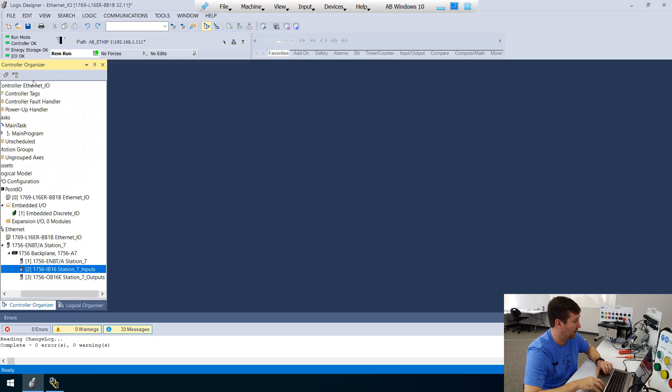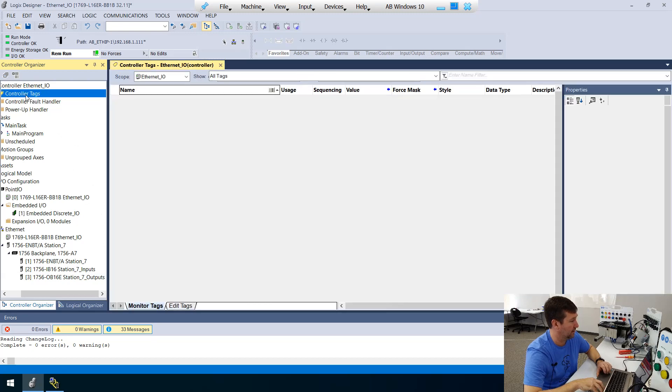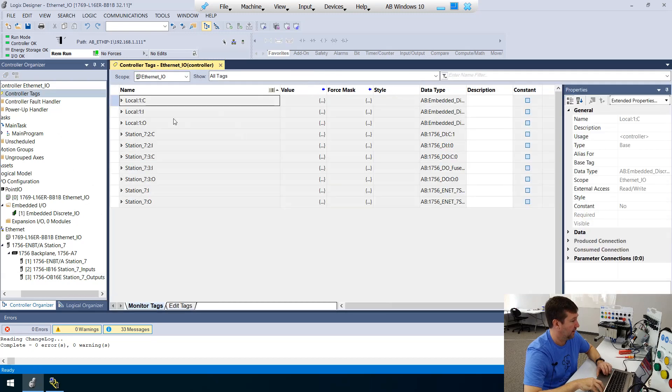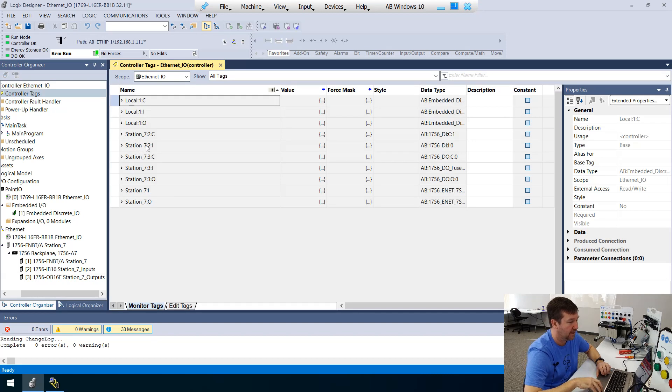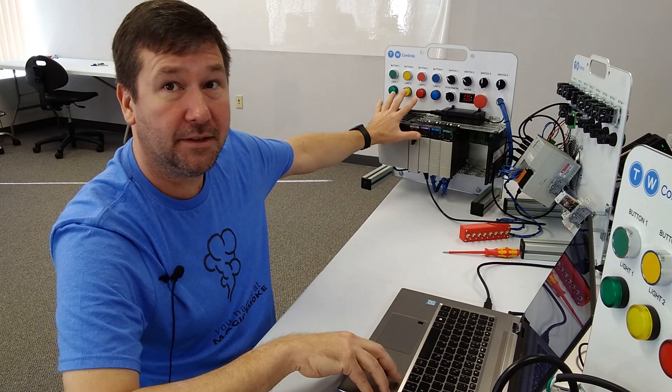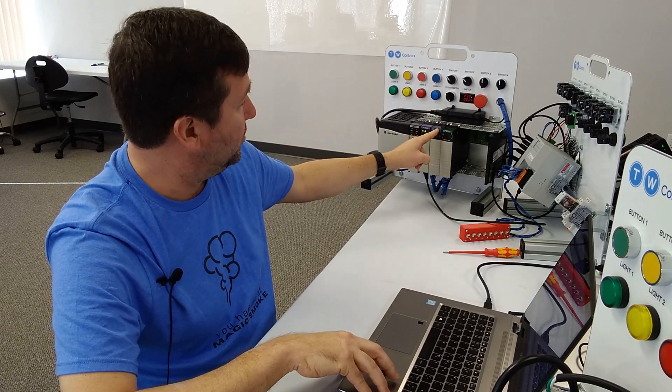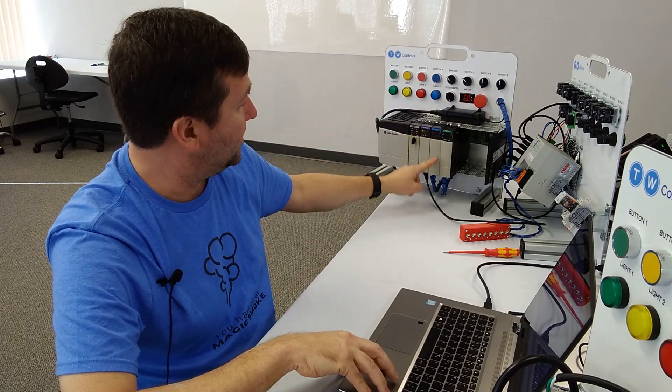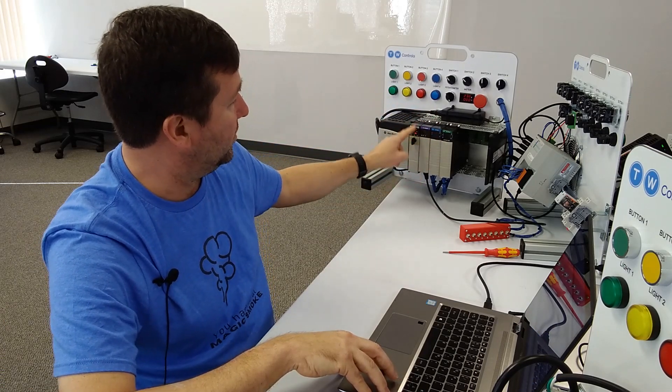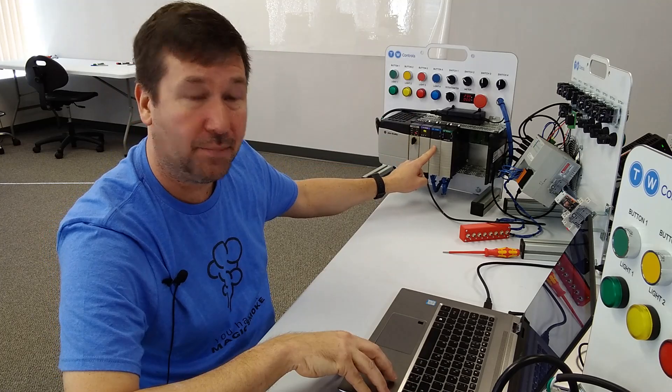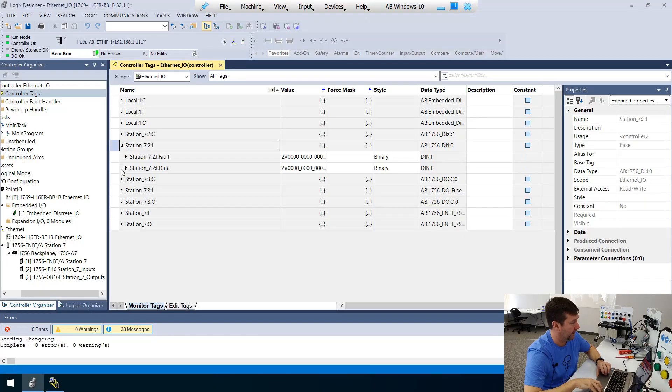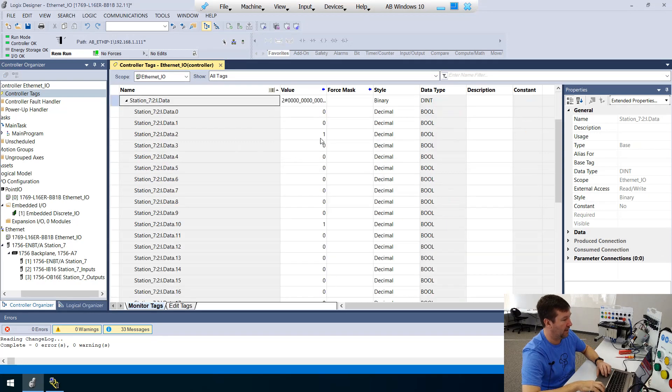Now, our IO is okay. And if we open up our controller tags, and we look down, we have station seven, colon two, colon I. So that's station seven. One. Two would be slot two. So zero, one, two. There's our inputs. And if I open it up, and I open up our data, we see that we already have a one in a few boxes.